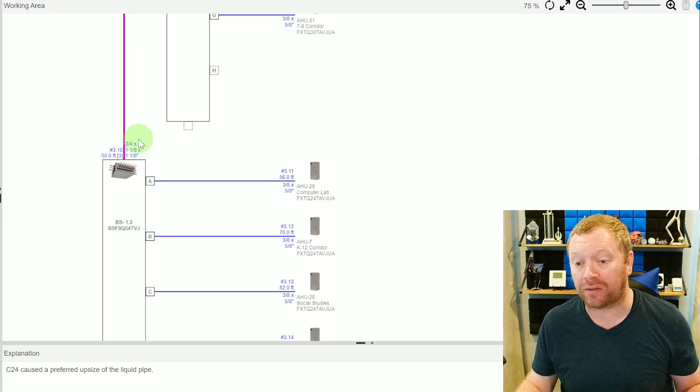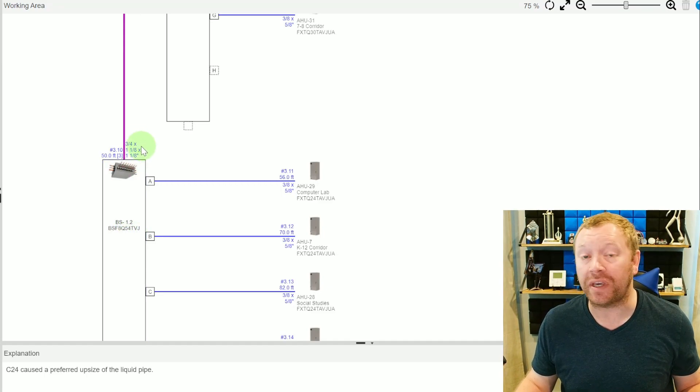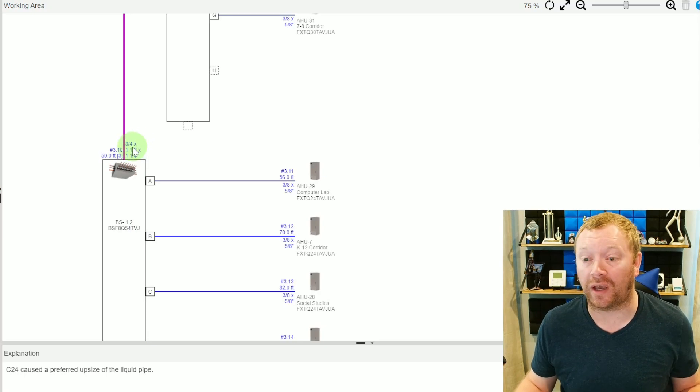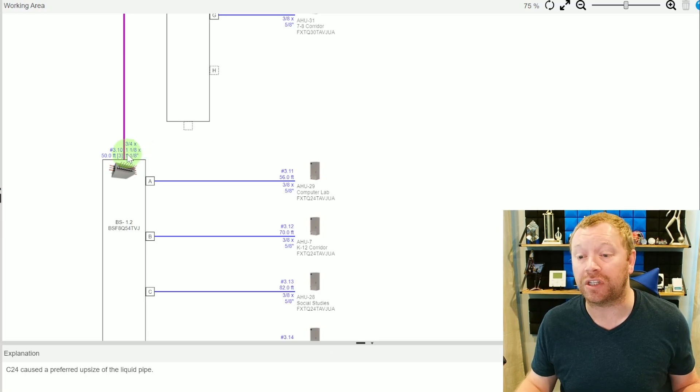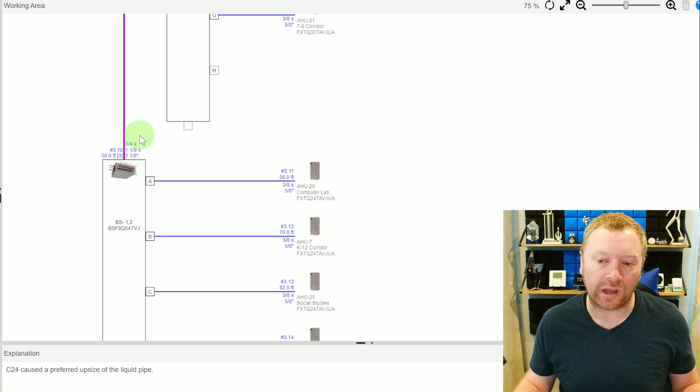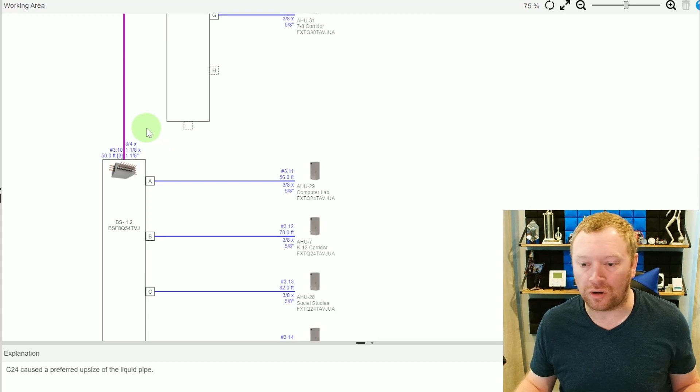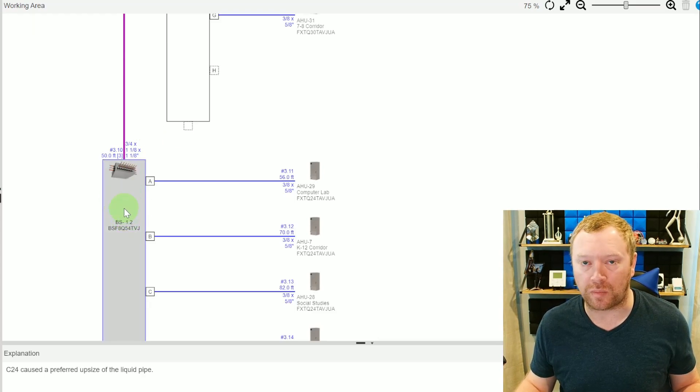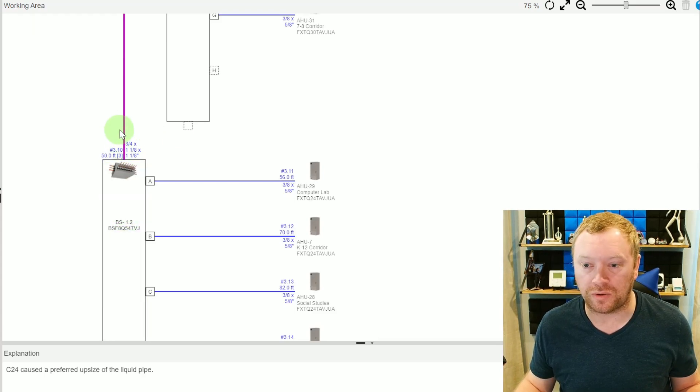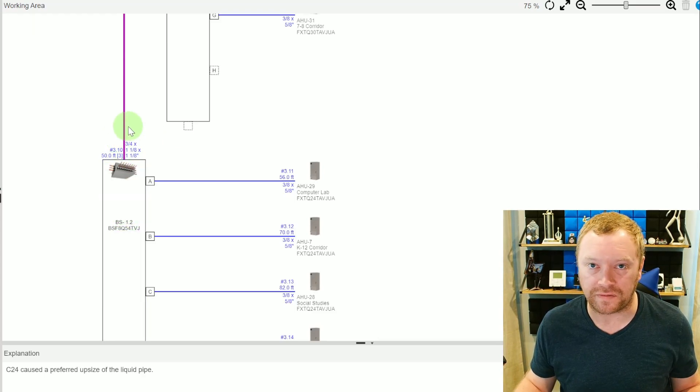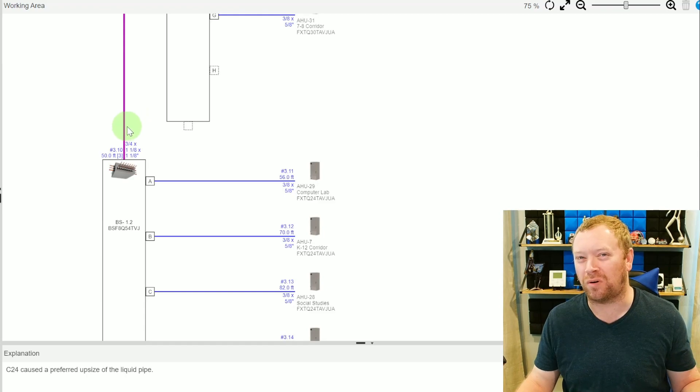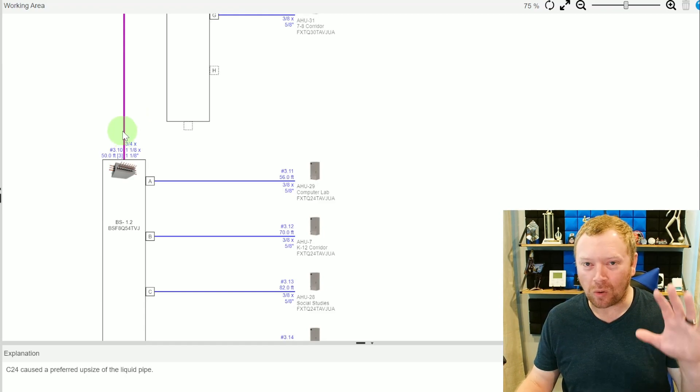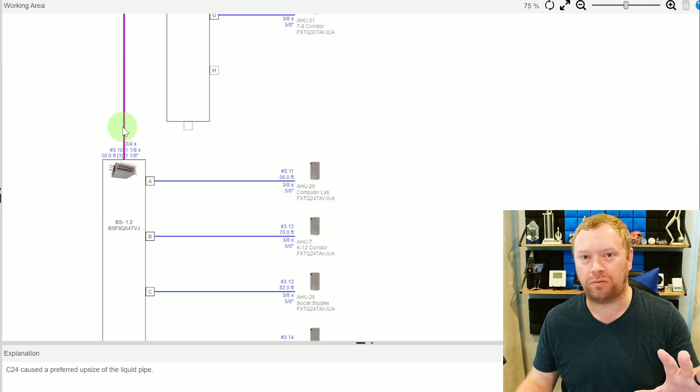So this pipe here actually needed to be, I'm just going to go ahead and punch in 50 feet because that should push us over. This length here during the design was supposed to be a three quarter inch line going to BS1.1 originally. So then they changed it. They came back and they're like, oh yeah, well, we installed a five eighths liquid line. I'm like, well, then you need to change it. They're like, well, you know what? We made a mistake. This is actually BS1.2 and we only ran it five feet. And I'm like, whoa, whoa, whoa, what? Like hold the phone.